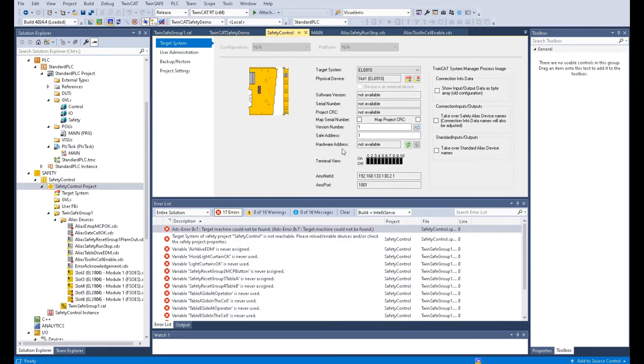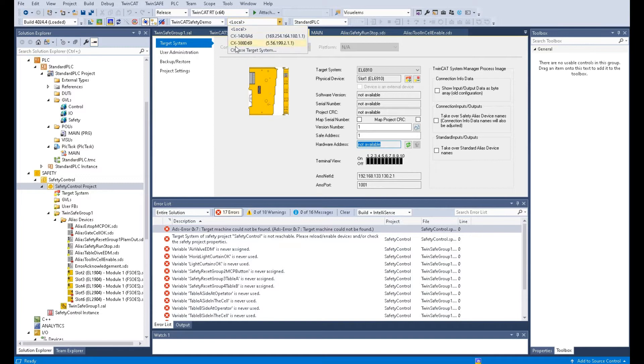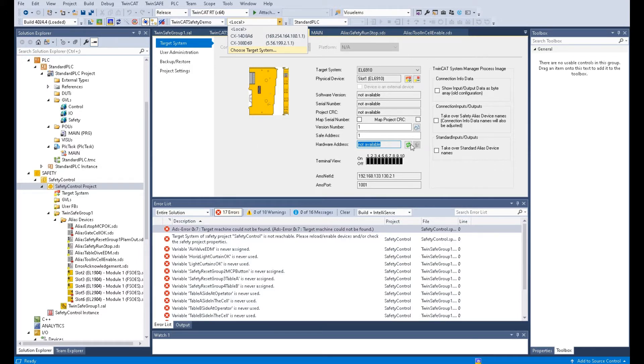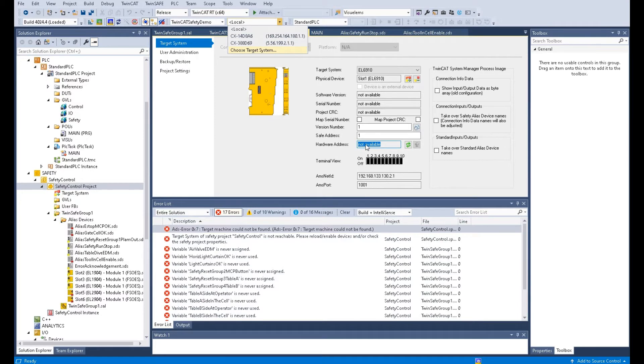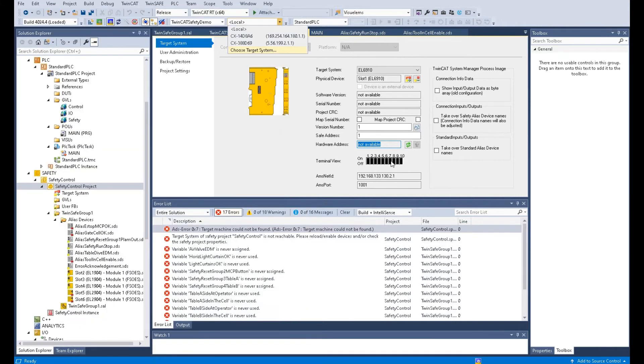To find this hardware address, we need to go online, connect the actual controller, and switch your controller into configuration mode. Select refresh, go upload, upload the actual hardware setting. That setting is at the DIP switch at the side of that EL6900 or 6910 controller. Like here.